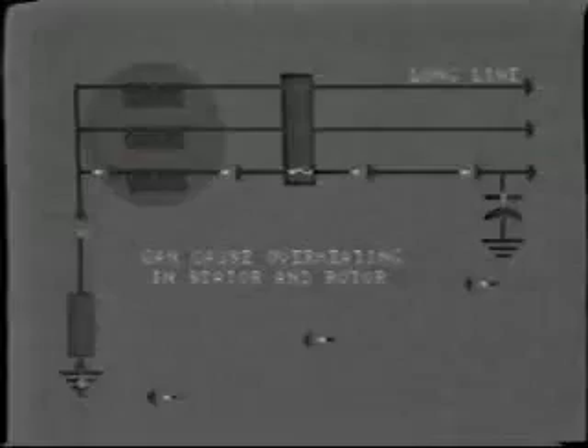A special problem that may occur with the large unit generator is flashover of one breaker pole. This can occur where the generator through the breaker is connected to a long high voltage line open at the far end with resultant high capacitance and high voltage. When the breaker is opened at no load, one phase may flash over and maintain capacitive current flow out of the generator. Serious overheating could occur in the stator iron due to the capacitive current, and also in the rotor due to the high negative sequence components. The negative sequence current relay may not respond quickly enough to prevent damage.